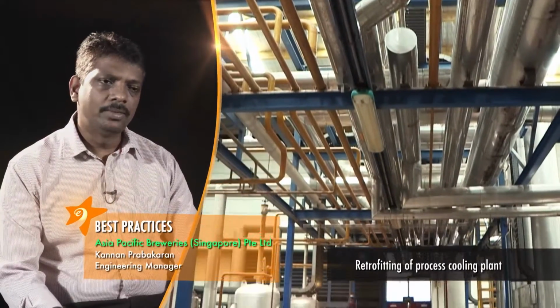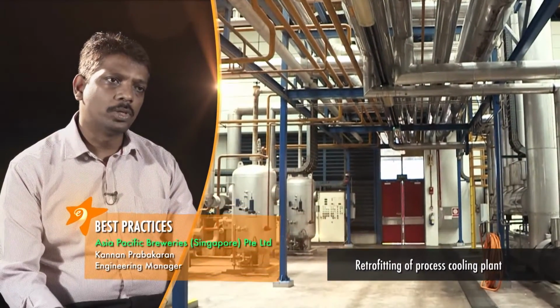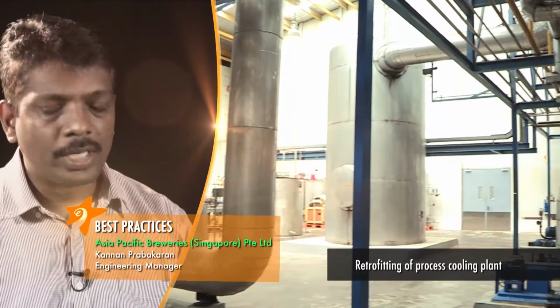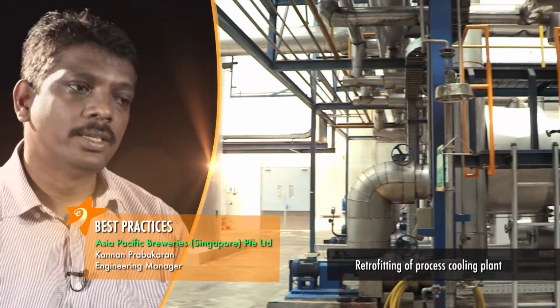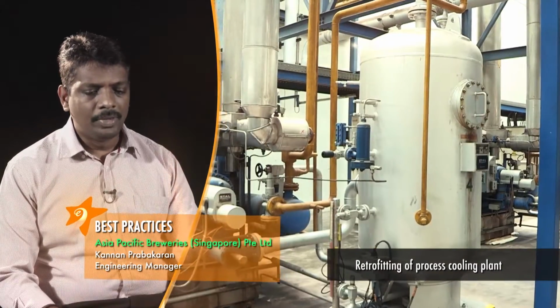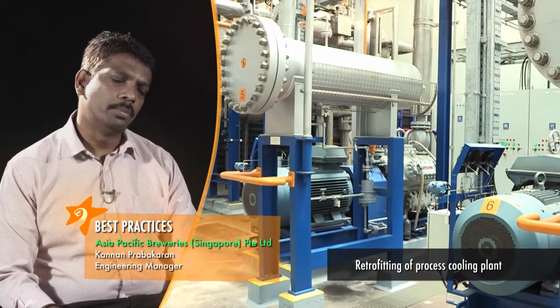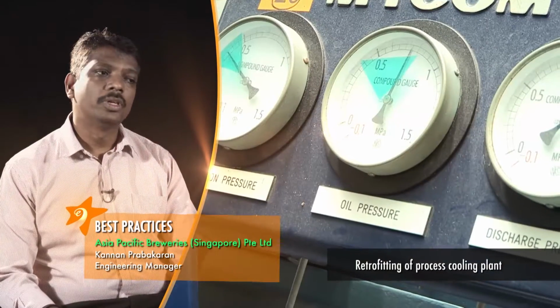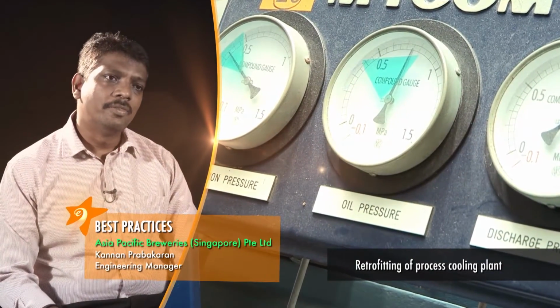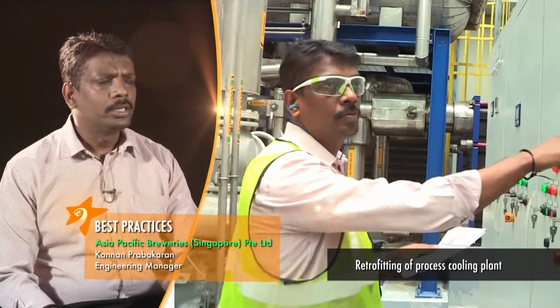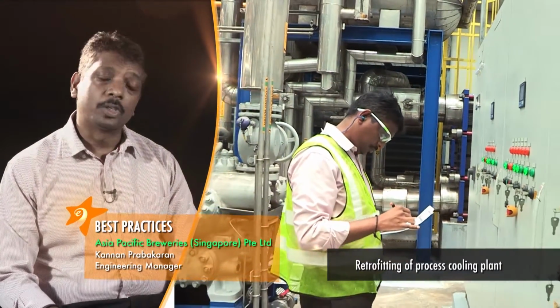In 2013, we had 620 kilowatts across 5 compressors. We took one unit out and modified it, and we got a new higher COP. In 2013, we were around 4.1 kilowatt hours per hectoliter of beer produced. After the retrofit, as well as some modification in the process, now, especially for 2016, we are at 3.37 kilowatt hours per hectoliter.